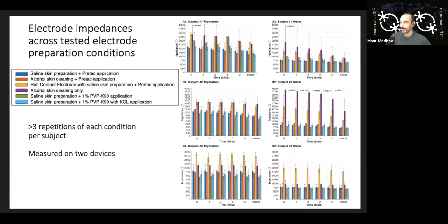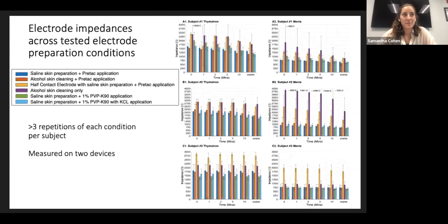But from the perspective of the ECT machine, is there, does it perform better with some subjects than others because of this? Yeah, so actually, when I was the subject, I would tend to go above the safety measurements of the machine. So it will not actually apply current if your static impedance is too high because then it becomes dangerous. So that was about 5,000 ohms. But most people don't have that problem.